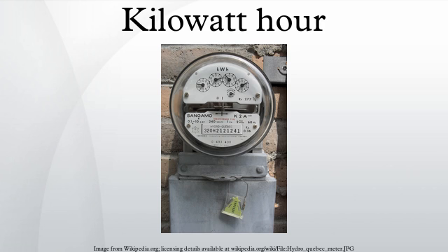A kilowatt-hour is the amount of energy equivalent to a steady power of 1 kilowatt running for 1 hour, or 3.6 megajoules. Whereas individual homes only pay for the kilowatt-hours consumed, commercial buildings and institutions also pay for peak power consumption. This compensates the power company for maintaining the infrastructure needed to provide higher than normal power. These charges show up on electricity bills in the form of demand charges.